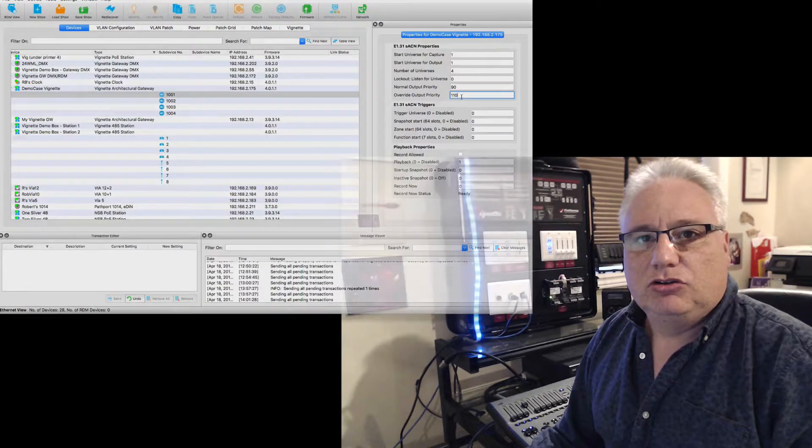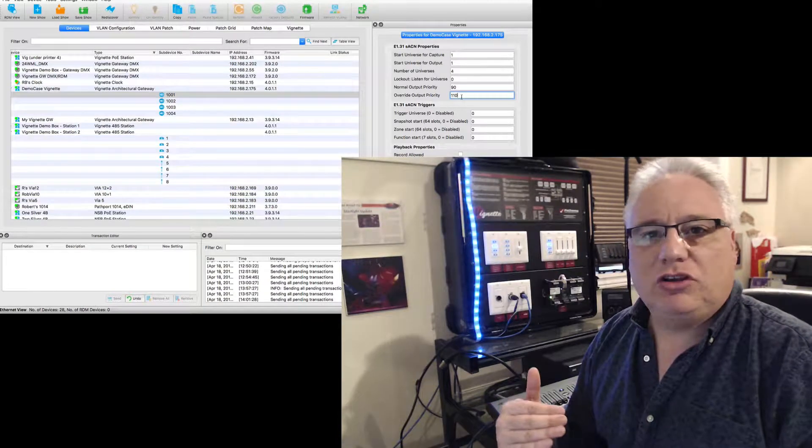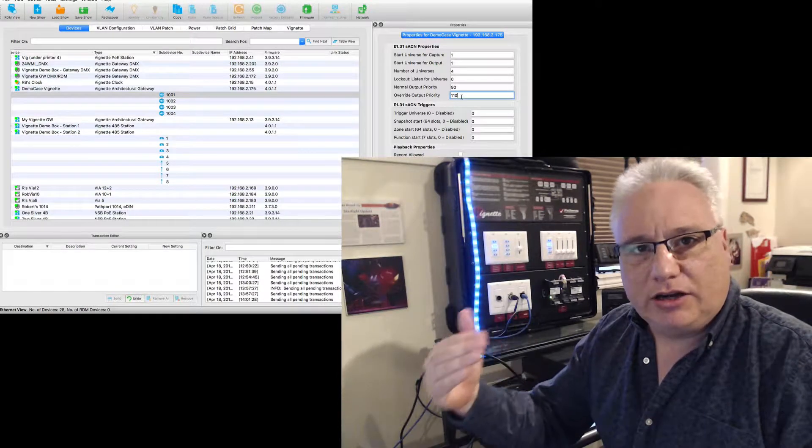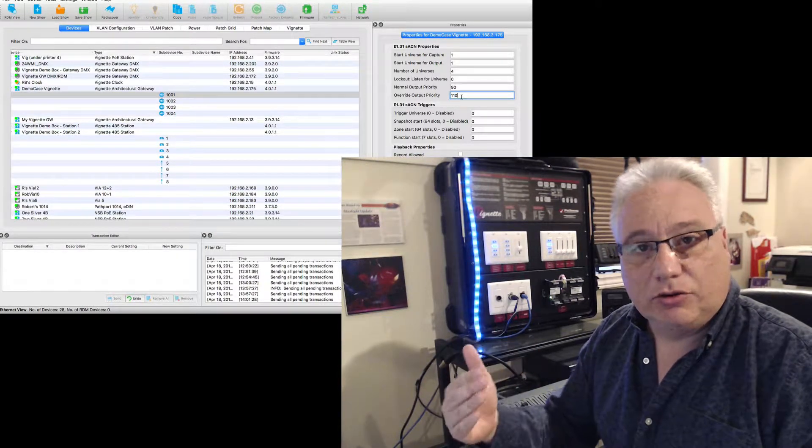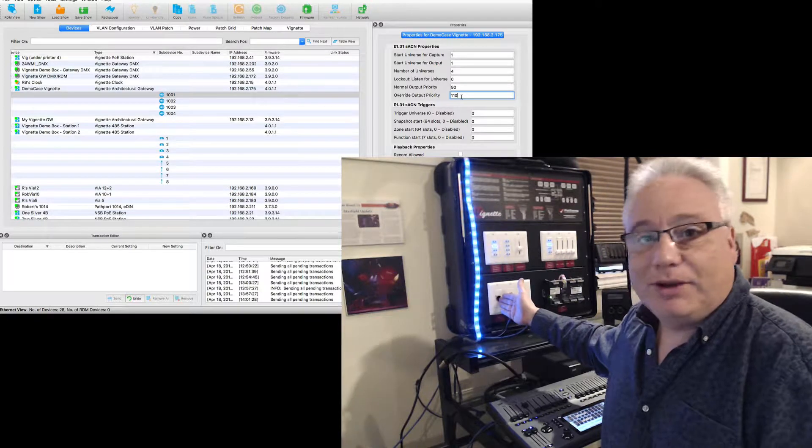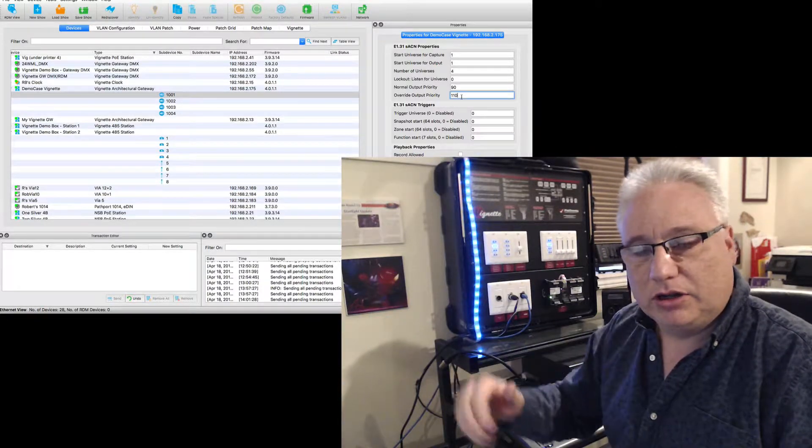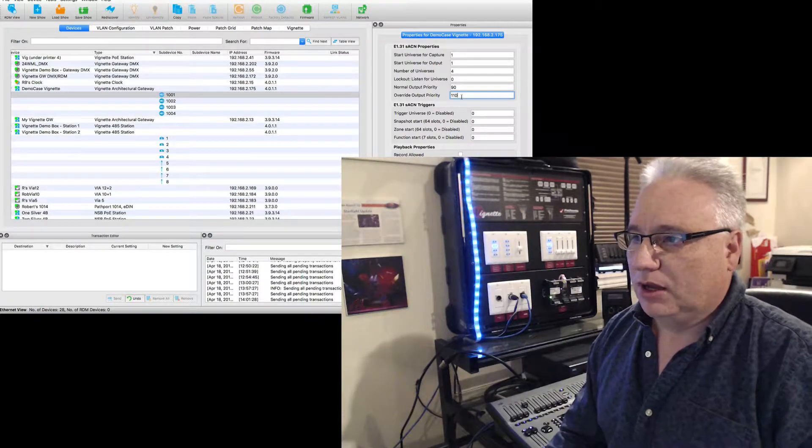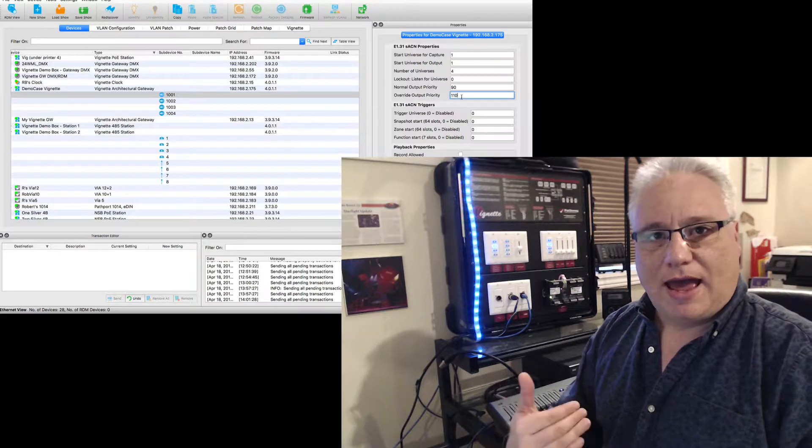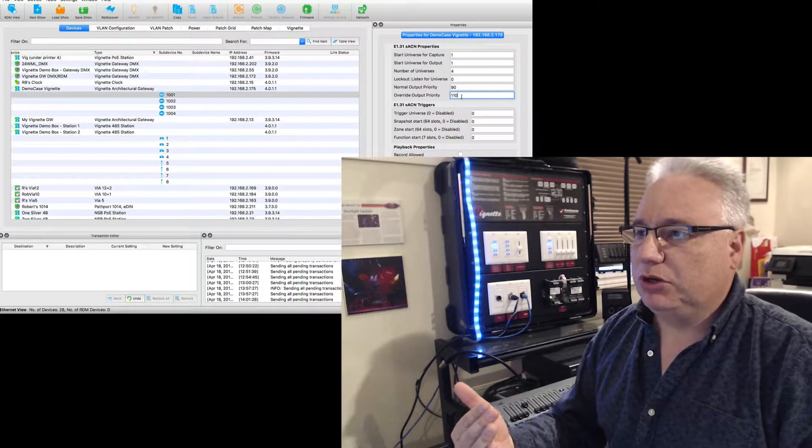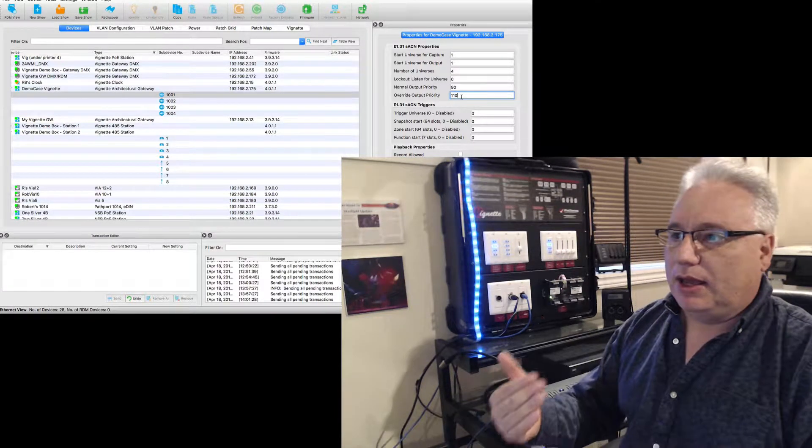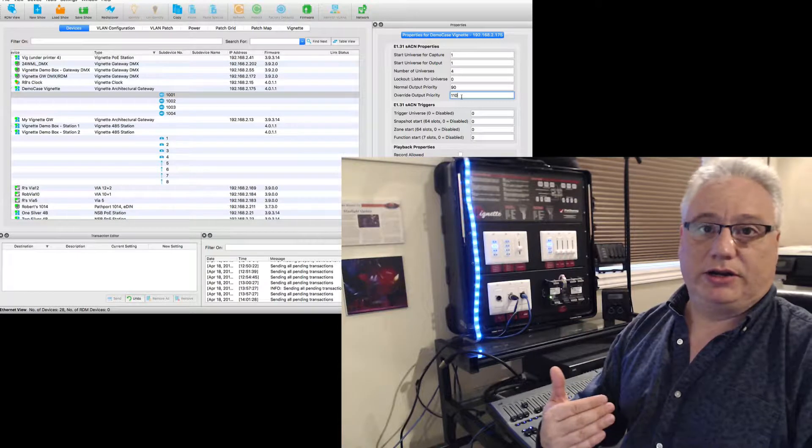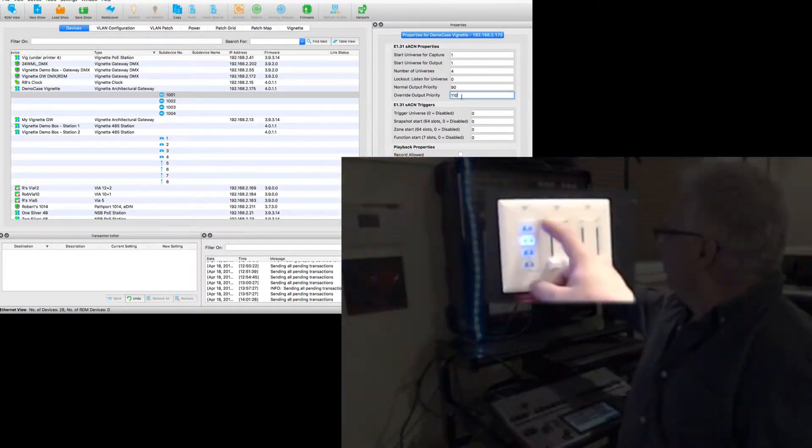Now there's another attribute, another priority called the override output priority, which is at 110. So to get it using this higher priority, which is above 100, which is where the DMX port comes in at priority 100, we need to have a button that switches between normal output priority and override output priority.